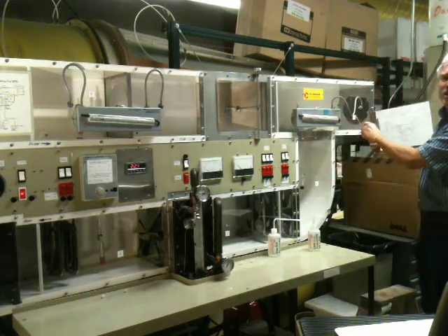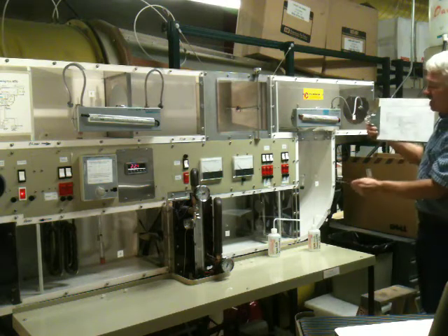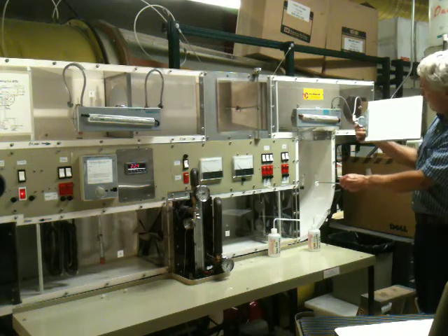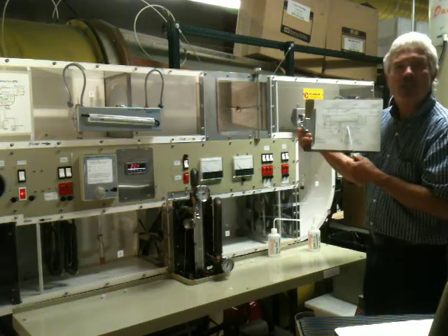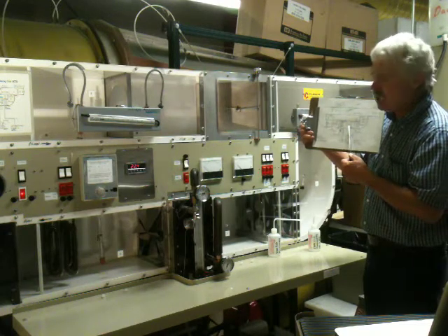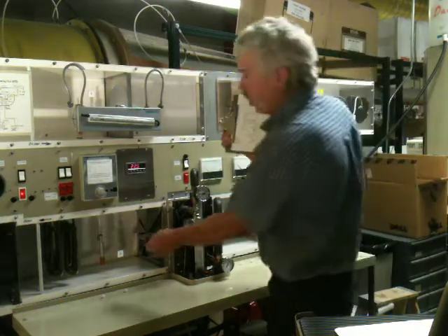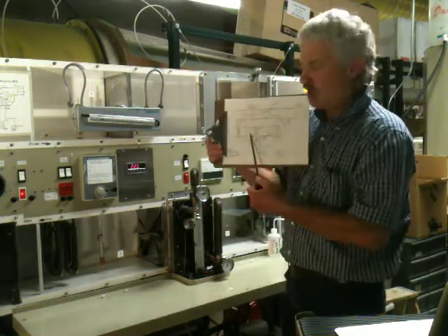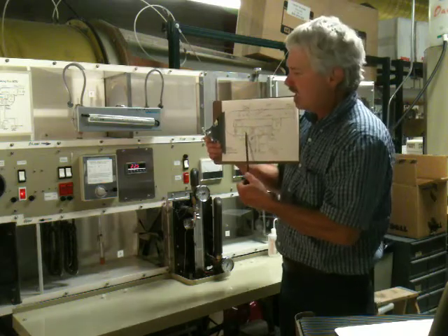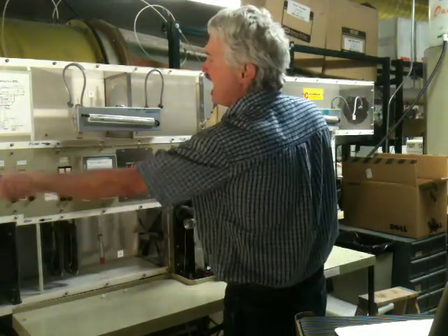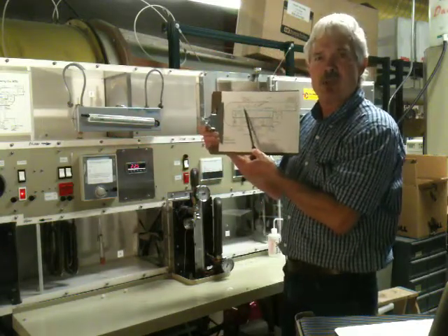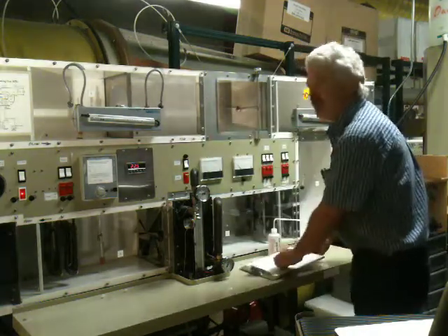So the first station is at the inlet here, station A. The second station is below the first static mixer, station B. The third station is downstream from the electric preheater and the steam injection manifold, that's C. The fourth station, D, is located downstream from the cooling unit. And then we go through the reheater, the fan, up again, and then finally the last station, E, is close to the exit from the unit. So again, at each place we're going to record dry bulb and wet bulb temperatures. Let me take the camera off and we'll look in a little more detail here.